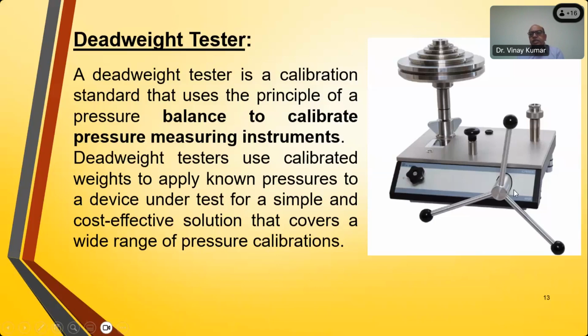In this construction there is a pump and a storage oil tank, and the piston and cylinder assembly. The measuring device we can put on the right side here. We can connect any calibrating and measuring device and measure the pressure. We can compare the pressure of that device by balancing the pressure between the dead weight and the measuring device. This is based upon Pascal's principle, and this dead weight tester is used to cover a wide range of pressure.